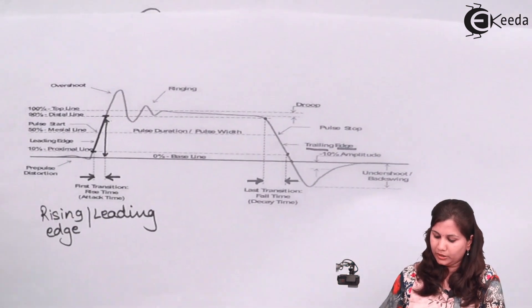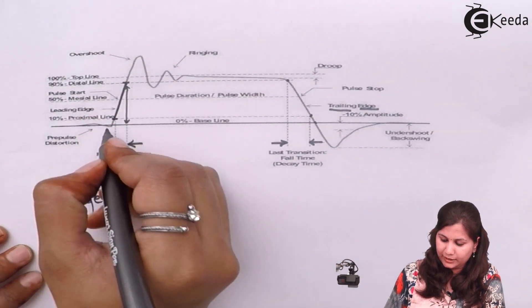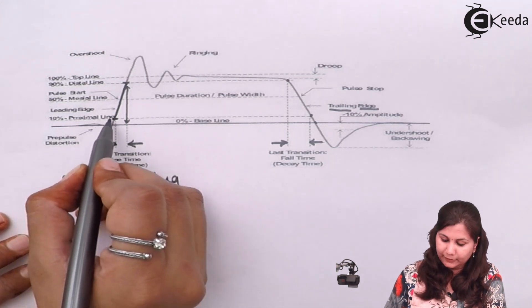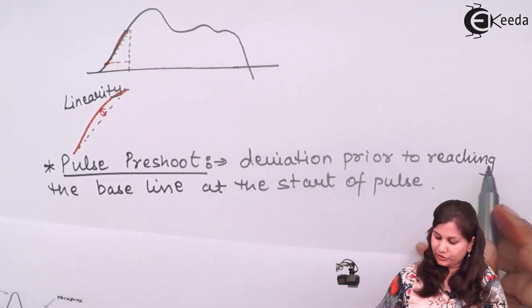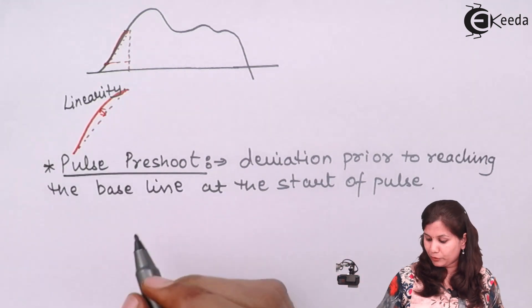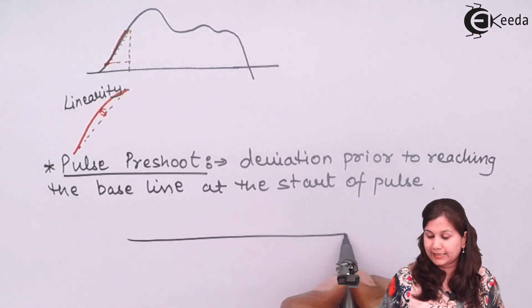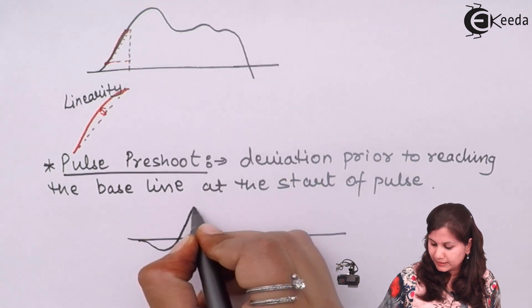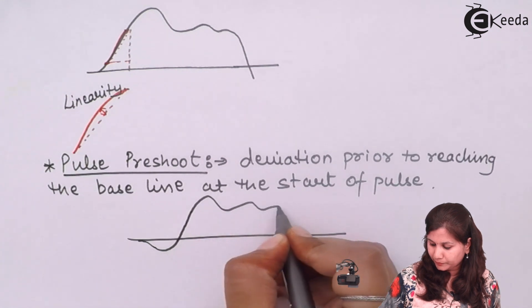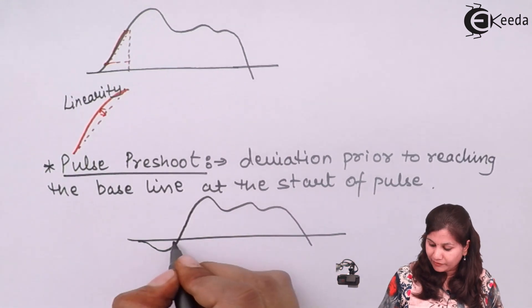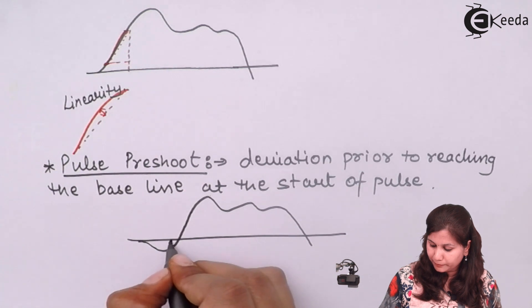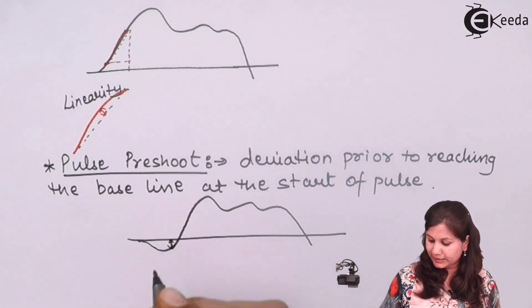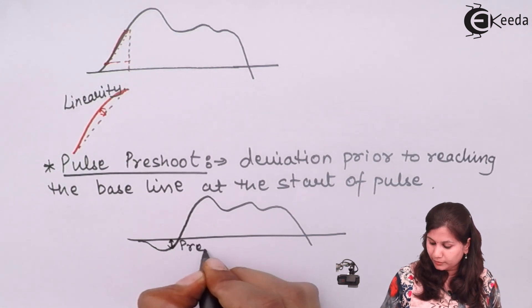When the pulse is starting, if the pulse has any deviation from the baseline before the start of the pulse — that is, it is somewhat deviated from the baseline before the pulse begins — that is called the pre-shoot.